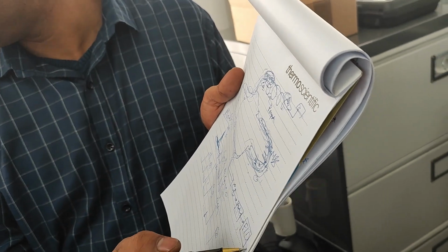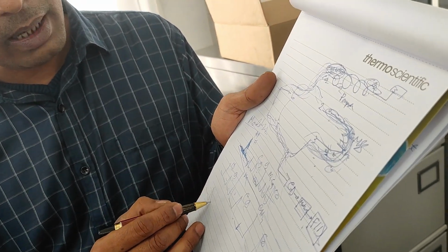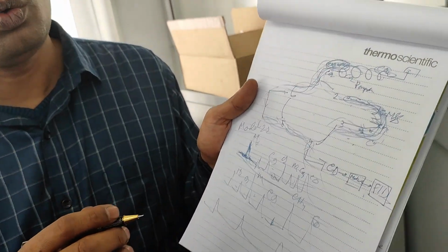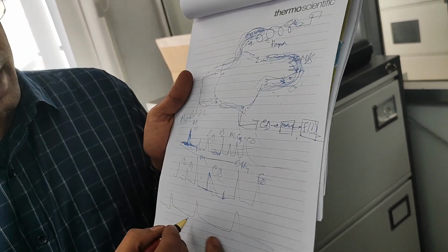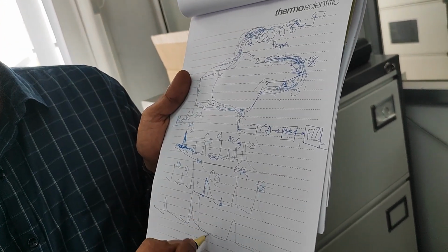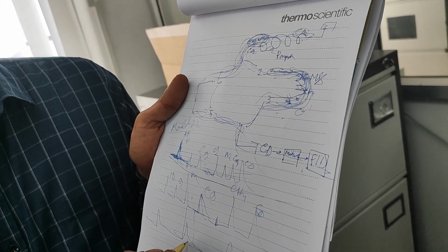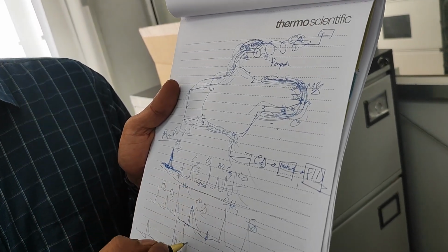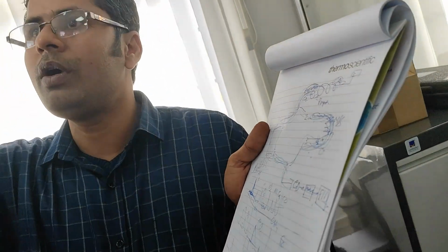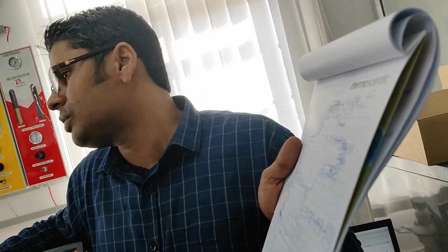At the same time, the same sample goes through the methanizer and FID, so we can get some peaks in FID also. If CO2 is at percentage level, you will get a peak in TCD. At the same time, you will get a very large saturated peak in FID, because it's converted into methane and FID sensitivity is very high, that peak will go beyond my capacity. So that time you have to delete this peak and take only this peak.